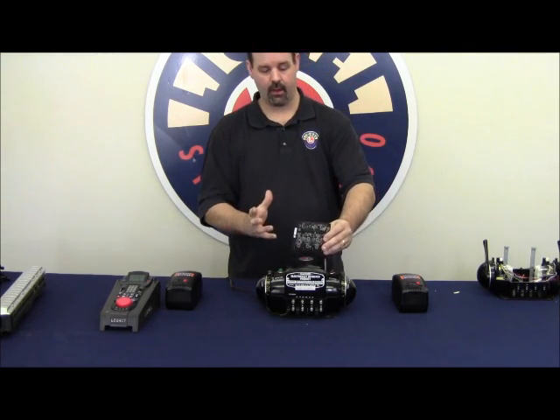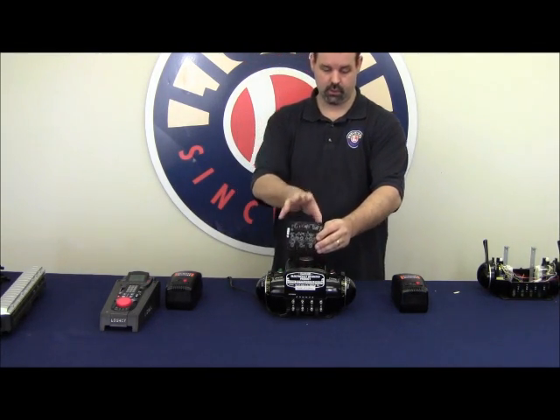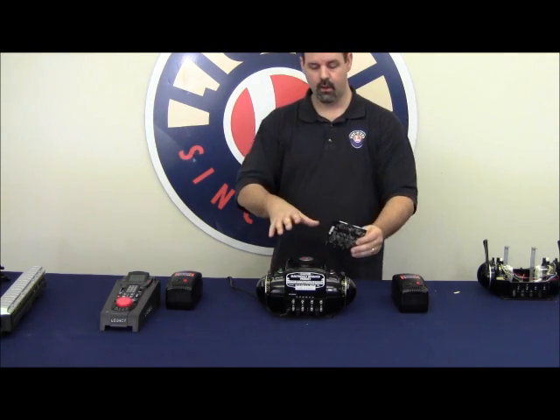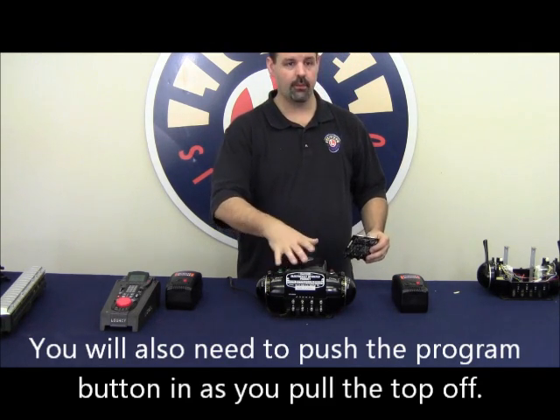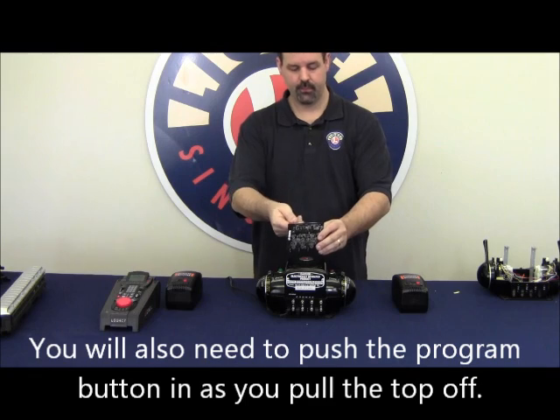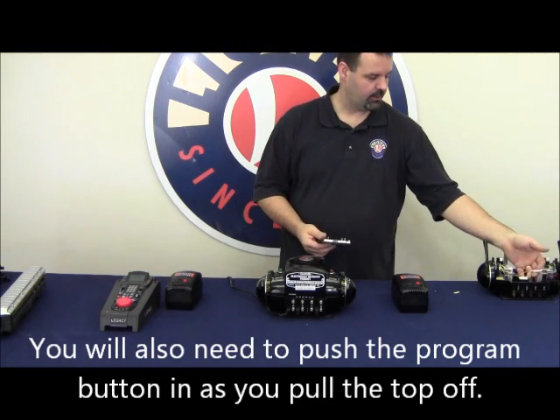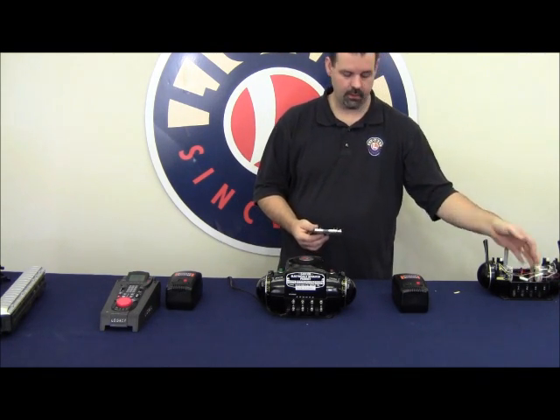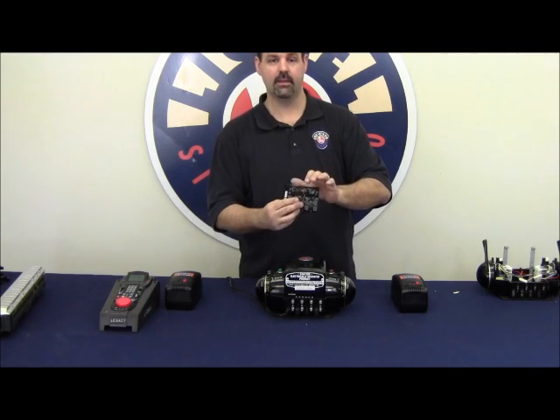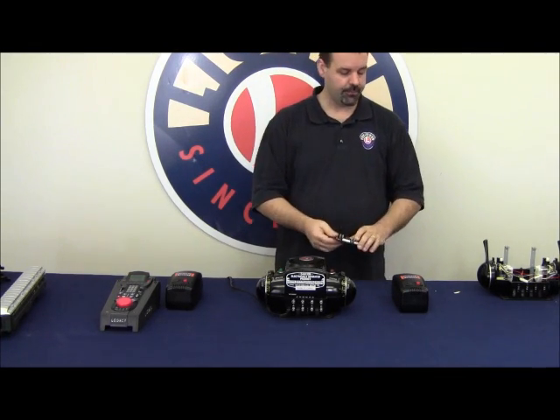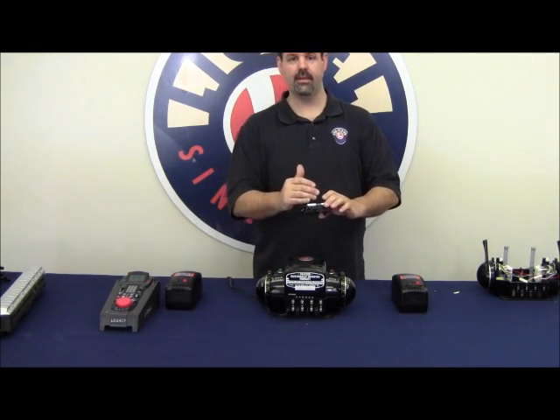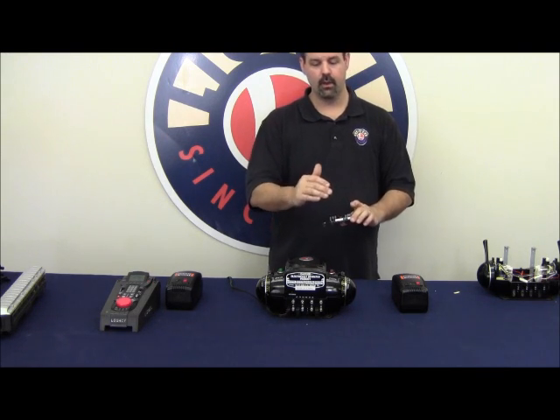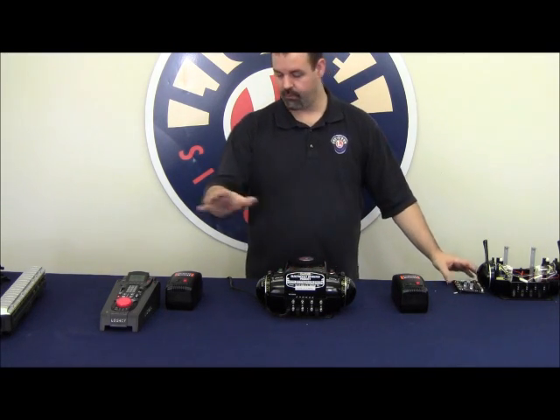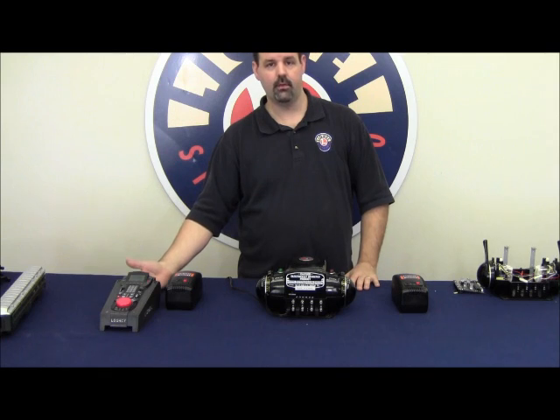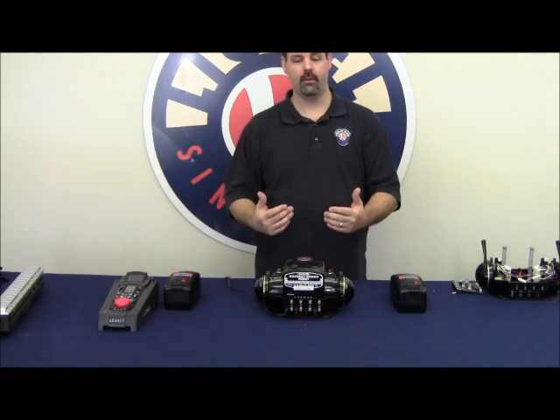You don't have to take this out—it's a real bear to get this circuit board out of the casing. You just take the 4 screws off, pull the lid off, unplug the terminals and connectors in here, and you can actually replace this processor in place. By putting that ZWPCS01 processor in, it prevents the ZW from detecting the 455 signal out of the Legacy base as a halt command.